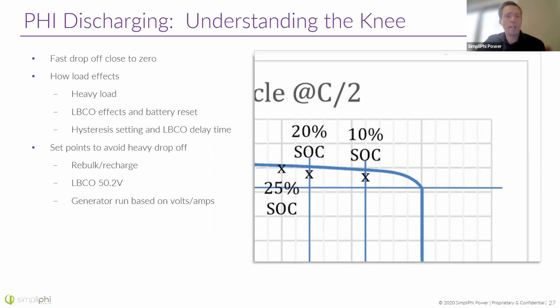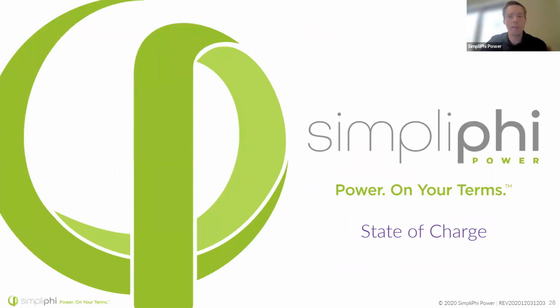So, set points: we encourage using a low battery cutout on your equipment of 50.2 volts, which will leave 20% state of charge remaining in the battery. If you're heavily loading batteries, you can use a slightly lower low battery cutout, which will just prevent the inverter from shutting down when the battery actually has a state of charge of more like 30% or 25%. So if you have questions about that, we can go back through it.